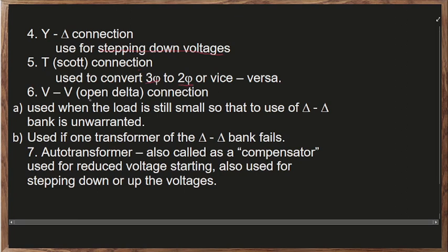Then the V to V or open delta connection, no? Sa V to V, yung isang linya mo is a neutral, no? Neutral yung isang linya, kunyari line 1, line 2, line 3. If that is connected open delta, so ito yung magiging neutral mo, habang ito, this is a current carrying wire, so live or hot wire. Okay? Habang ito naman is a hot wire. So ang disadvantage lang nito is unlike the proper delta, nahahati din yung KVA rating ng iyong transformer, no?